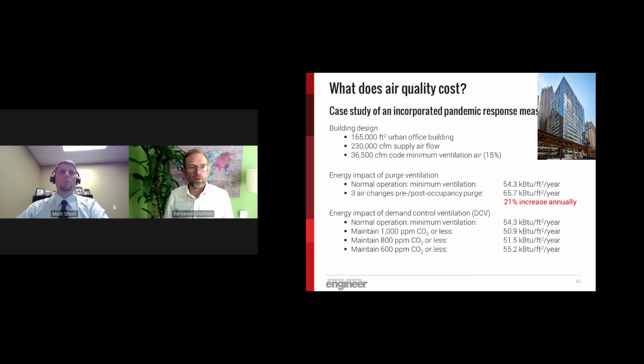A real brief case study on the cost of this. We did a case study in a building in Chicago, and we weren't able to actually do this live because the building's not occupied. So we didn't use live data, but we put it in an energy model and simulated the cost of a couple different things. One of the recommendations was to do the purge ventilation, so the 3 air changes pre and post occupancy. Doing that every day of a working week, we found that it increased the annual energy of the building by 21%. This being a building in Chicago, it could vary depending on your climate, but 3 air changes pre and post occupancy is a lot of energy.